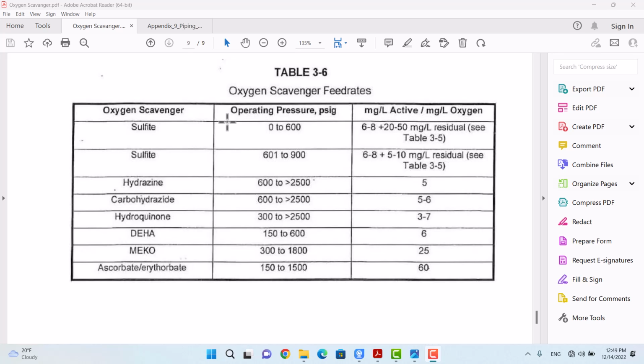DEHA. I made such a decision because, as I mentioned, unfortunately hydrazine can have some impacts on the environment and personal health. In the long term, personnel who are exposed to hydrazine excessively might suffer from cancer, or some serious illness resulting from exposure to hydrazine. So, because of these main reasons, we changed it to DEHA.